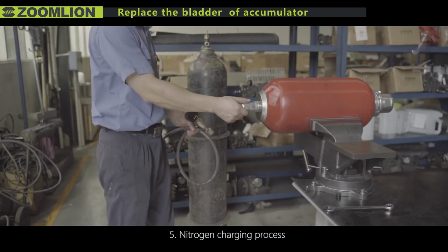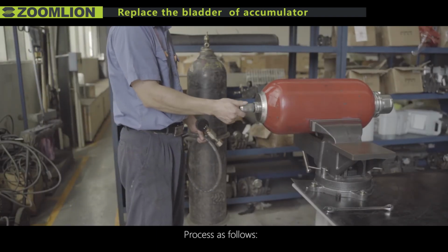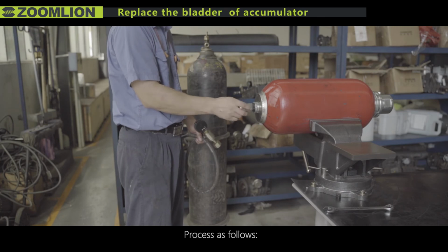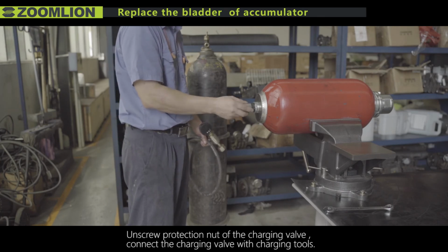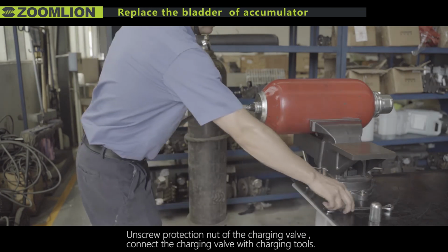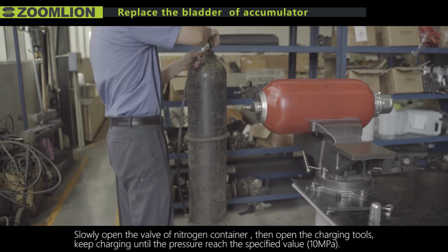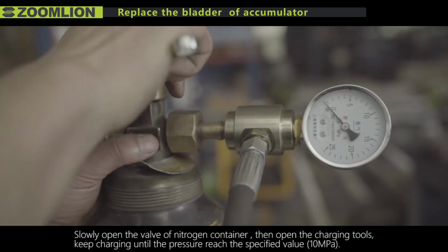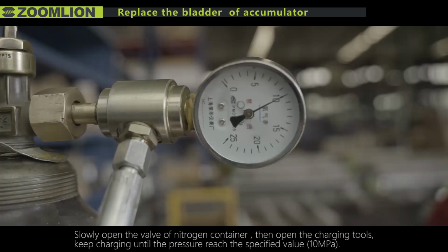5th, nitrogen charging process. Process as follows. Unscrew protection nut of the charging valve. Connect the charging valve with charging tools. Slowly open the valve of nitrogen container, then open the charging tools. Keep charging until the pressure reaches the specified value, 10 MPa.